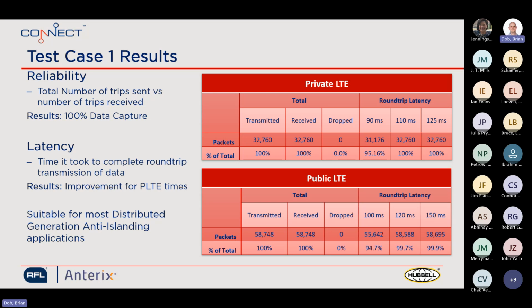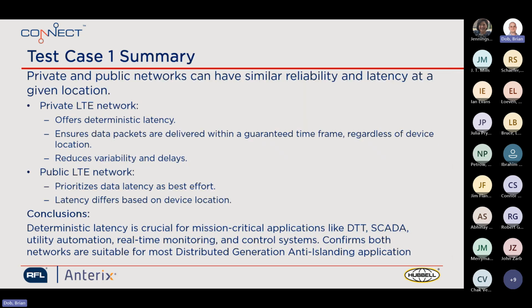So, I would say in general, worst case, we have here 150 milliseconds round trip. That's typically suitable for these distributed generation anti-islanding type applications. And we see we had good performance. And the variation in timing is a little bit better on the private LTE. It's more consistent. And so we explored that a bit in the next test case.